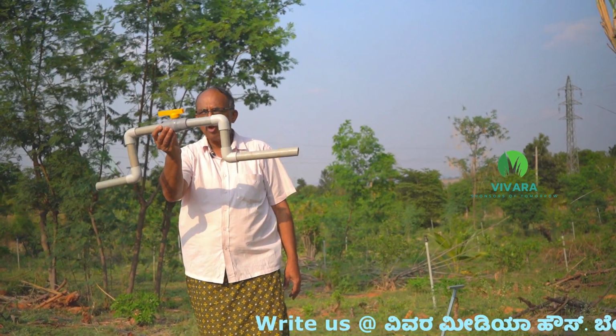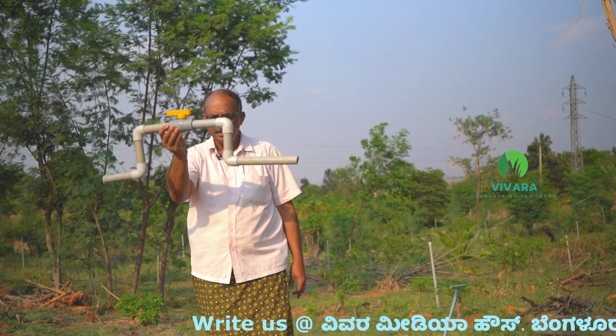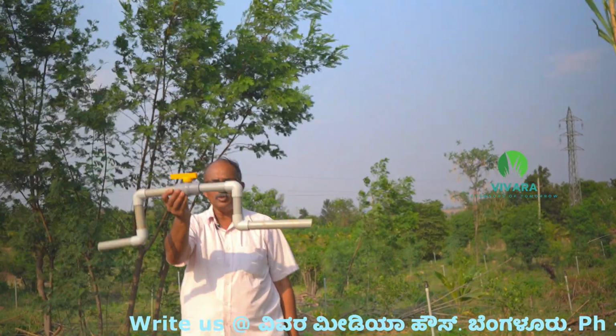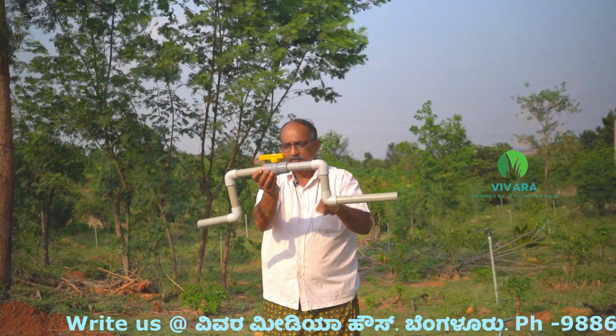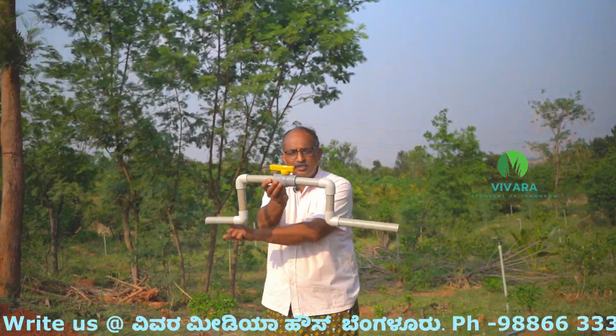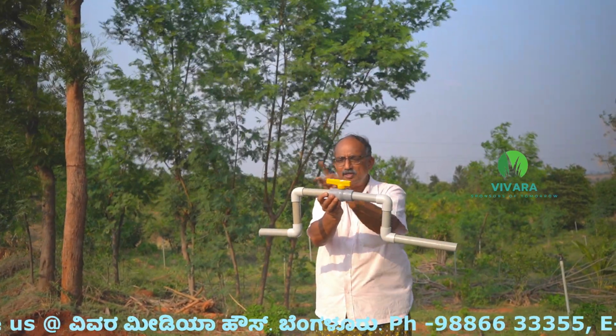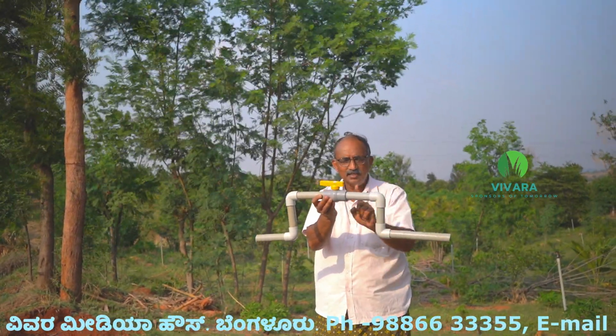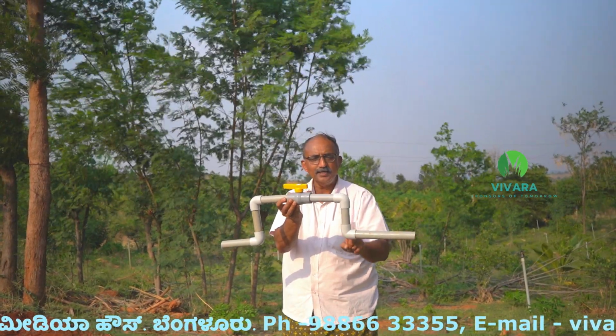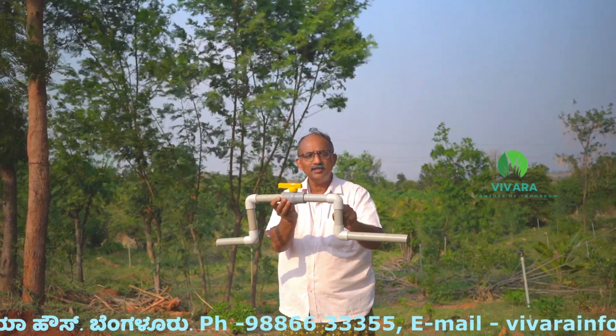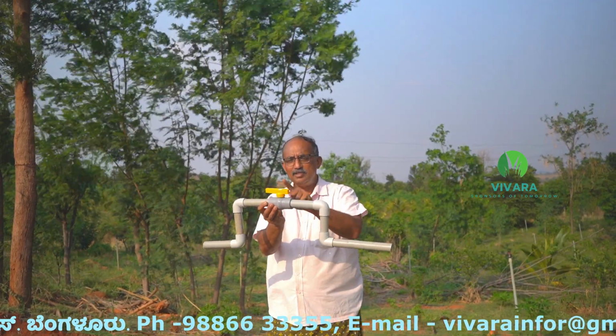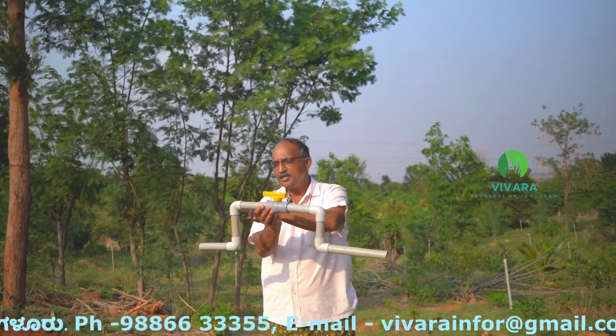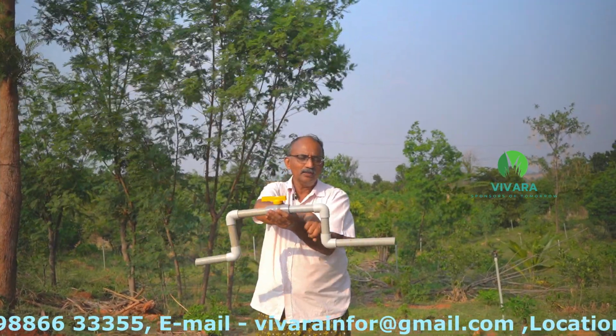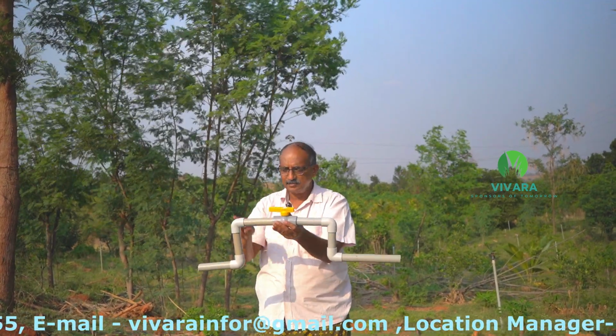There is a flaw in this, there is a disadvantage in this. What is that? As you simply visualize now, the water has to come from here and has to go out here. Just to put this control, we have done all this structure. One is the cost. Second, water comes and takes a 90-degree turn to surface level, takes another 90-degree turn, is decided by the valve control, then comes into this, takes another 90-degree turn, goes down to the pipeline depth and takes another 90-degree turn. We have 1, 2, 3, 4 elbows of 90 degrees.